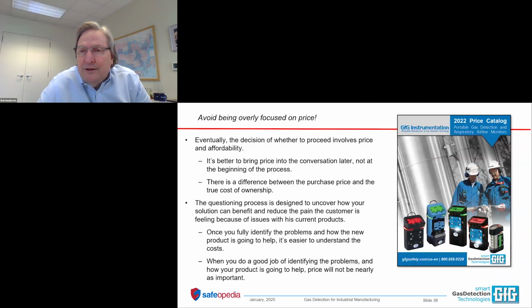Now, whether it's fixed or portable, my suggestion is, if eventually it is going to come down to price, price matters. But don't base the entire conversation and selection process on the initial purchase price. There is more to the ownership of the system than what you pay for the gas detection components that come in a couple of boxes. For fixed systems, your cost is going to include installation and ongoing maintenance and calibration. For the portables, it's going to include things like sensor replacement, the requirement to replace sensors frequently or less frequently. All of these issues can drive the true cost of ownership of that product.